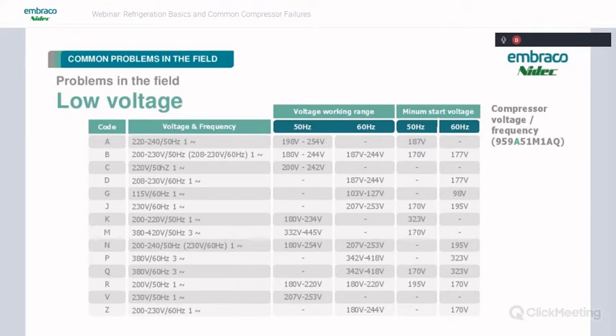So you can put your meter on it when the compressor's starting. If you've got an intermittent problem, make sure you're not dropping below 98 volts when that thing starts. And for the other one, the B voltage, 208, 230 volt, make sure it's not dropping below 177 volts.